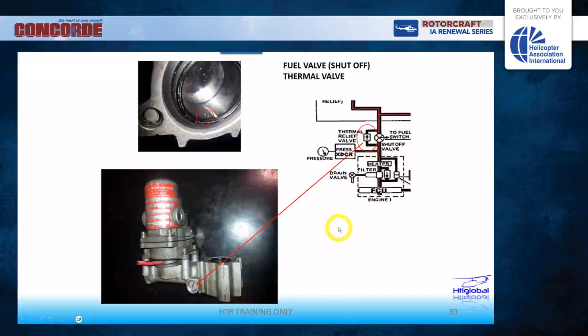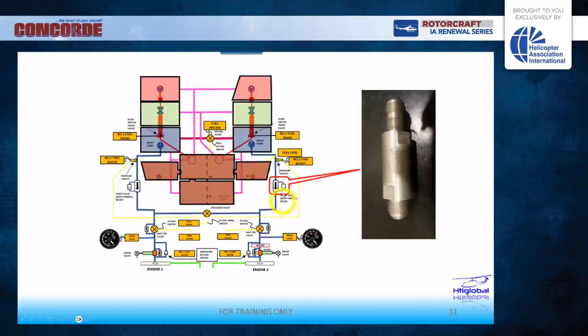The same thing happens here. These two valves, or check valves that I mentioned earlier, are located in the pilot area. After you shut down, this area is kind of confined and hot, so any building pressure due to temperature needs to be bled off. There's an orifice about 18 thousandths of an inch. When the fuel molecules compress to less than that, it bleeds off into the system, controlling the pressure in the area between the check valve and the fuel valve.